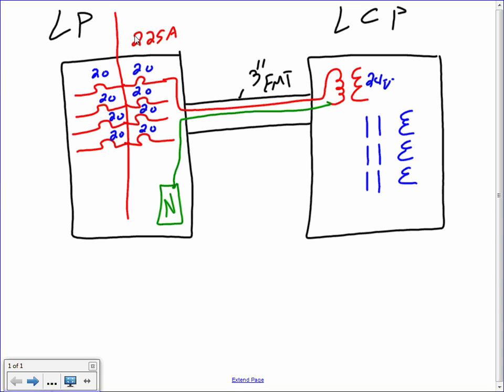The first thing they do when you have a lighting control panel is you need to power the lighting control panel. So what did they take? A 20 amp circuit, hot and a neutral, take it to a transformer. Can you guys see the transformer? And this transformer takes the voltage from 120 volt to one side and converts it to 24 volt. Can I have thumbs up, Chad?